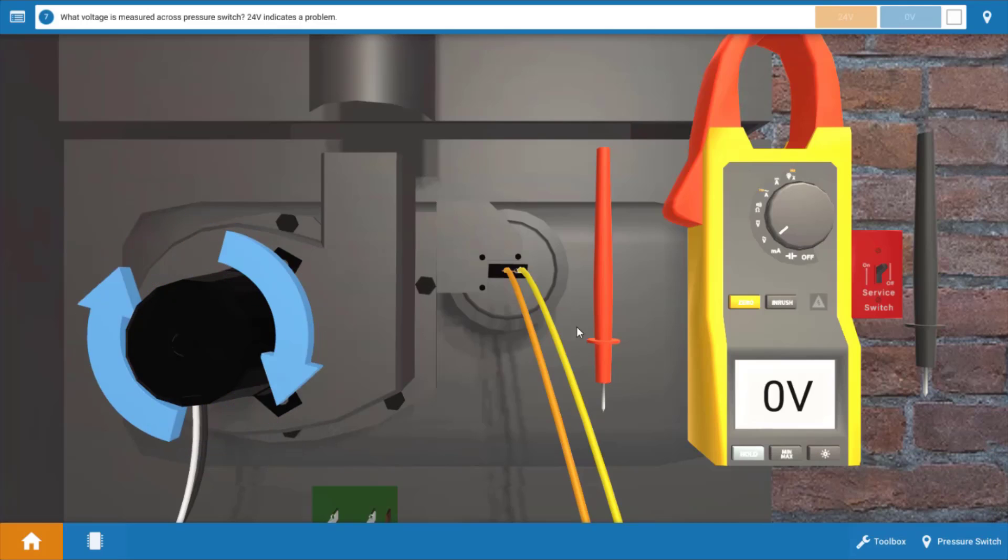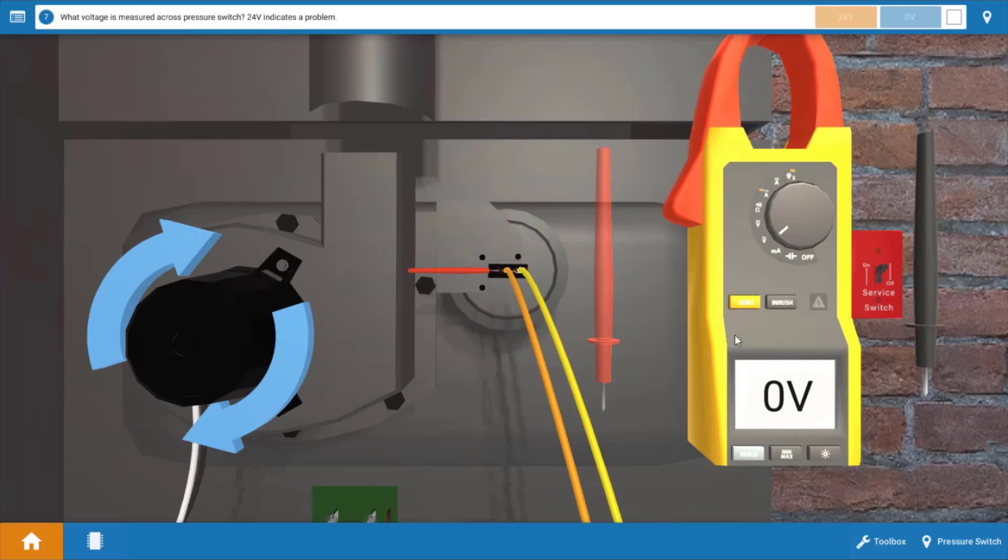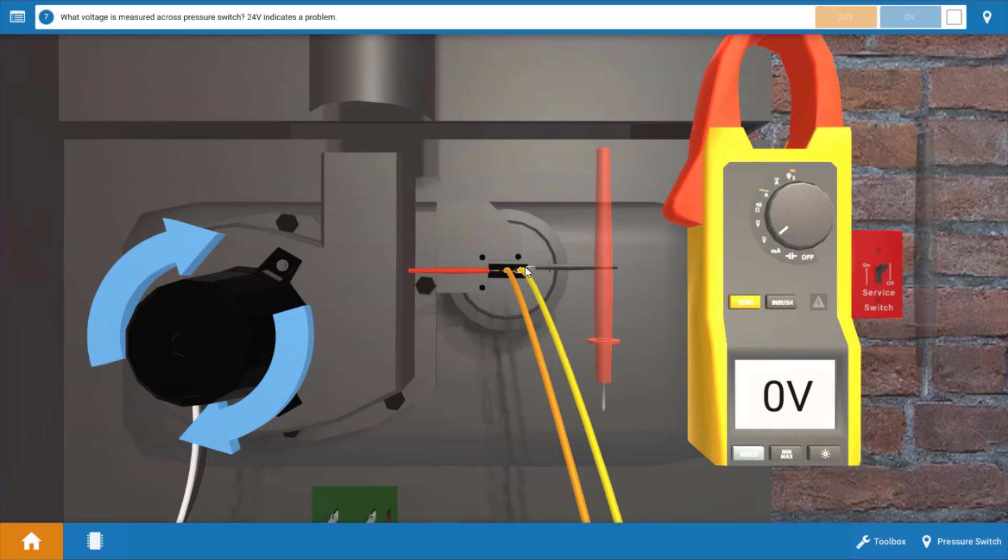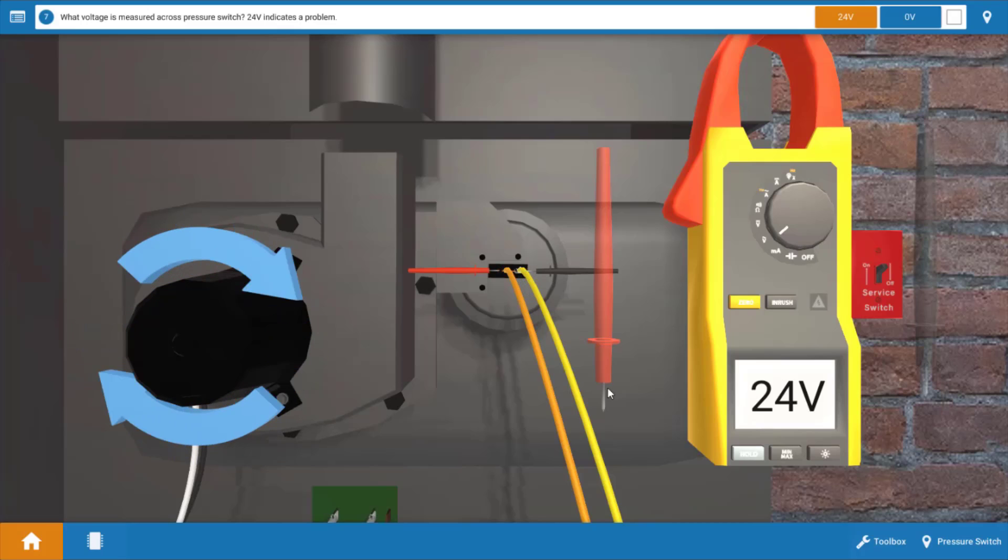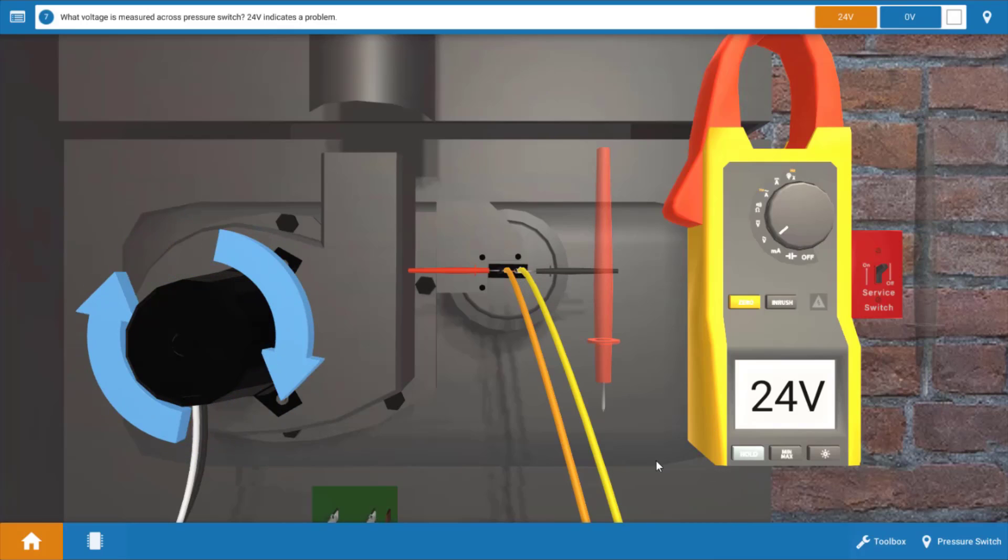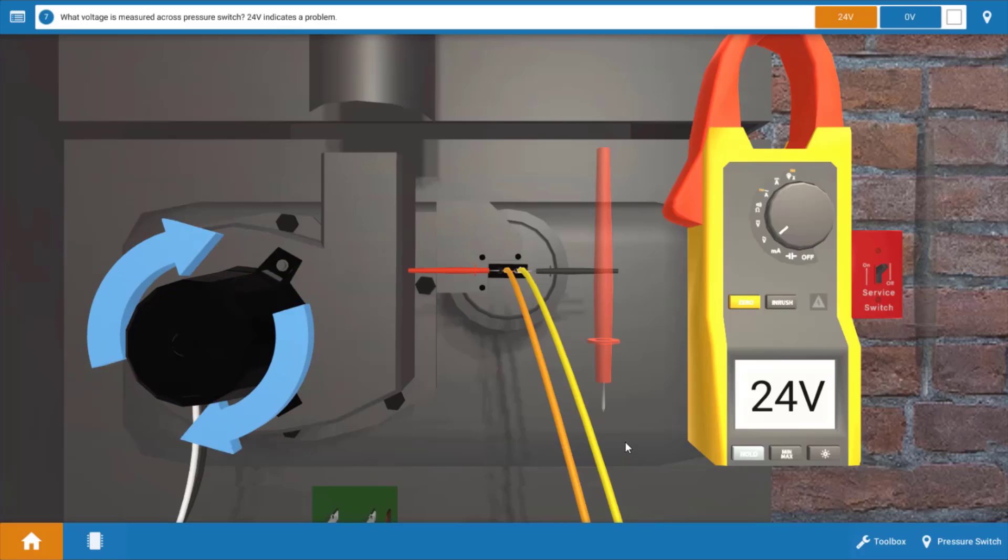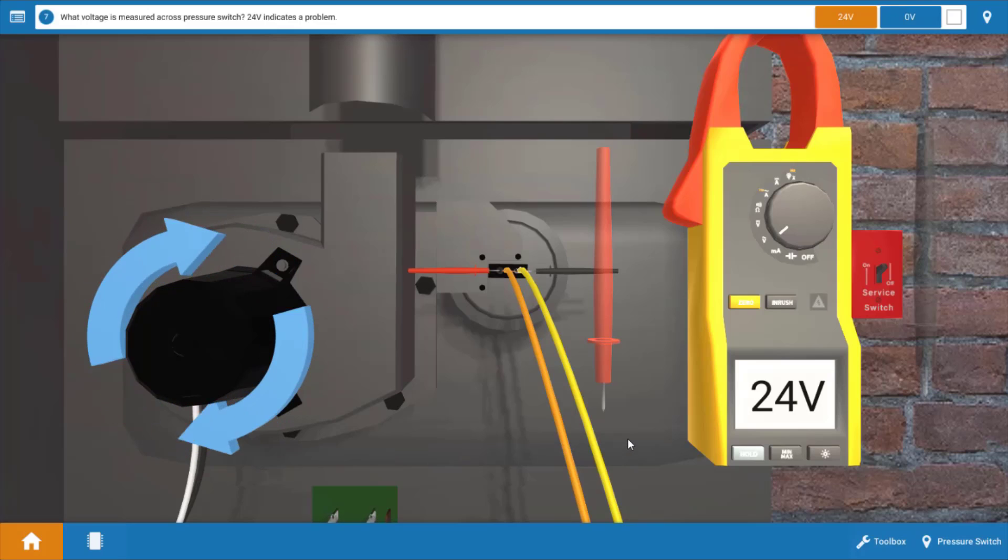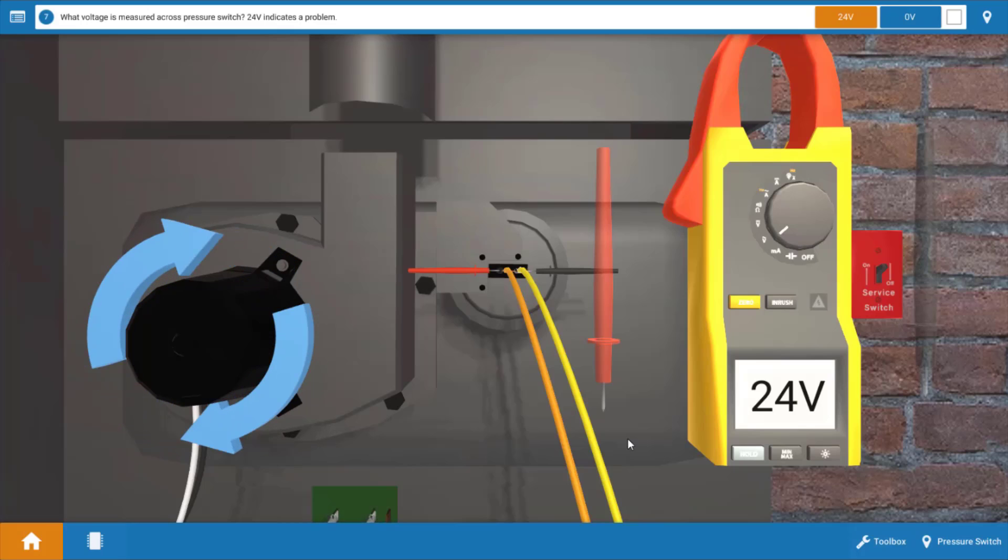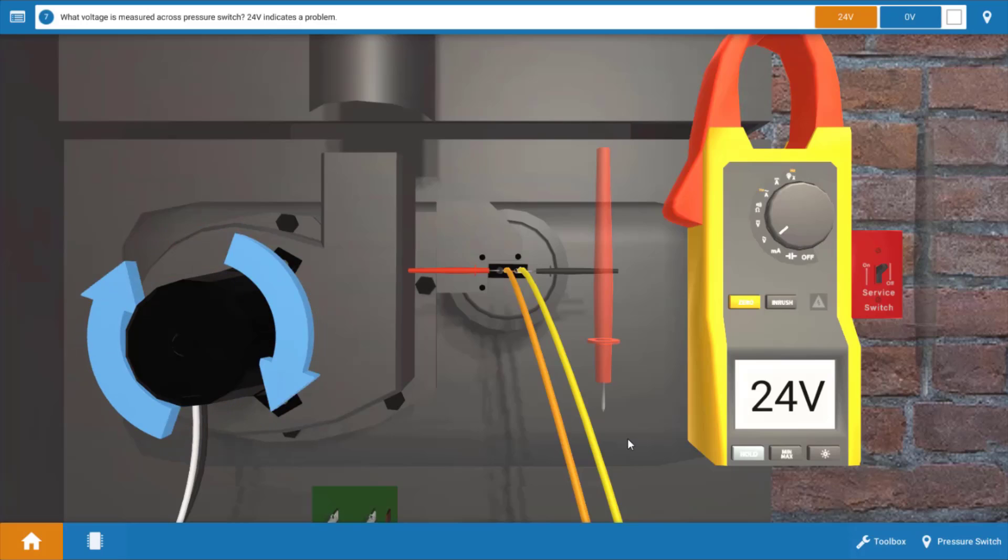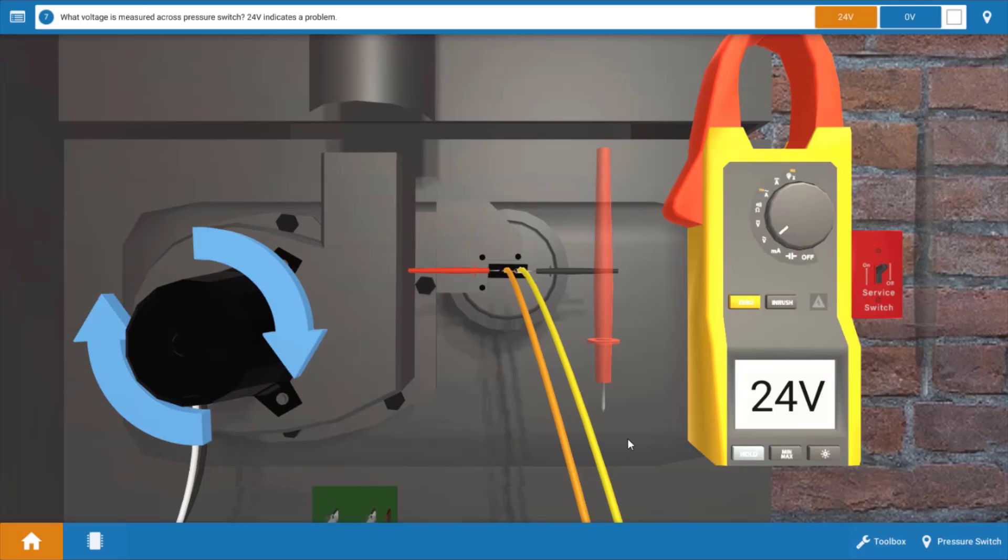So let's place our leads across the contacts of the pressure switch and see what we've got for voltage here. Now if it's closed we should get zero volts but in fact we have 24 volts. Now this indicates the pressure switch is open so we don't have a problem with the igniter here. The igniter's not glowing simply because the pressure switch didn't prove safe airflow so the IFC won't send power to the igniter.